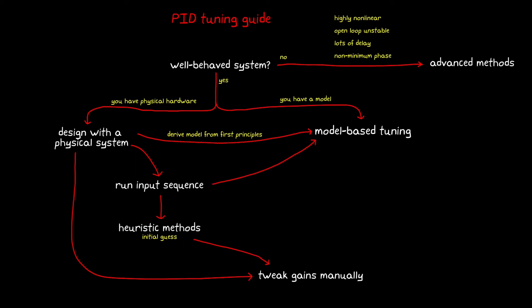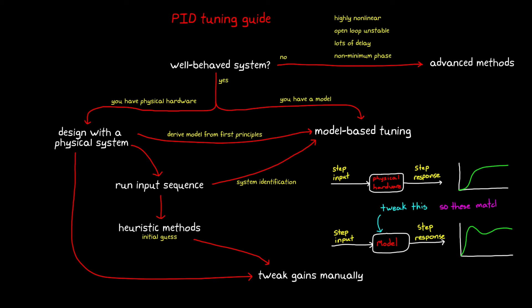An alternative way to develop a model is to use system identification techniques. System ID uses a measured response from the hardware, often a step response, and then finds an optimal set of model coefficients to match, as close as possible, the two responses.